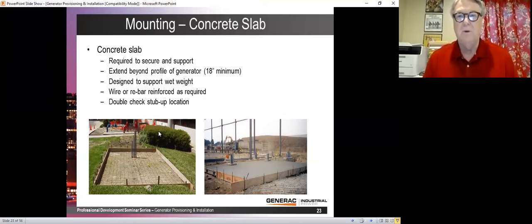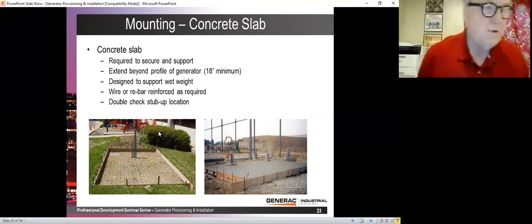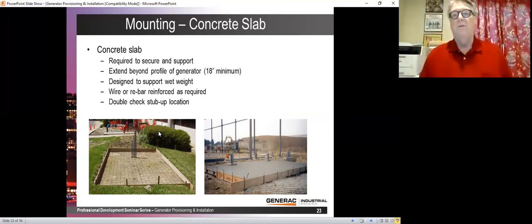It's nice in the rain to be able to walk on the cement and service the generator. But the code actually only says you really have to have cement under the actual skid of the generator itself. So exactly how to do the cement pad we can get into if you would like to call us on any particular generator. Typically, we like to see an 8-inch pad minimum with 3 inches above grade.